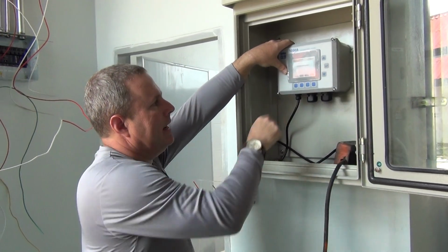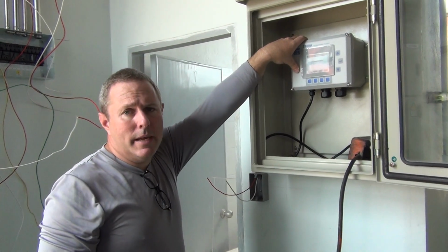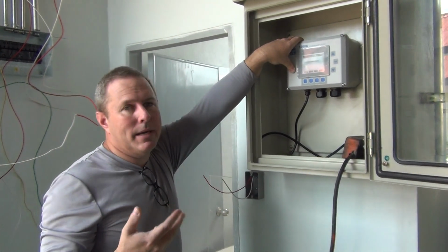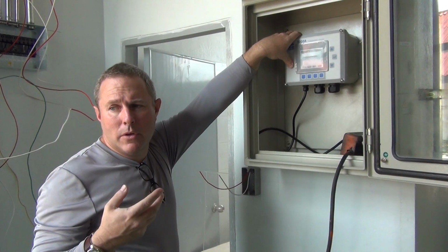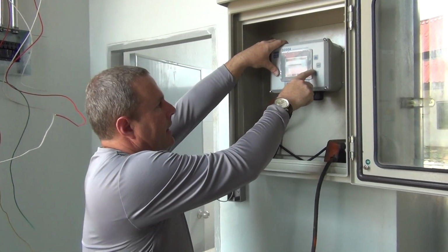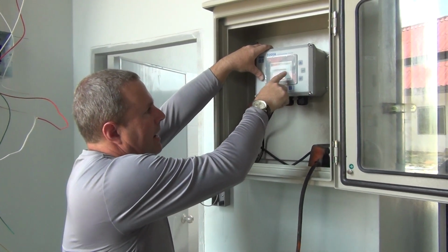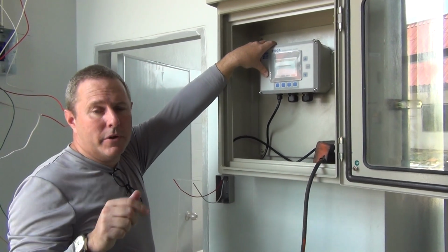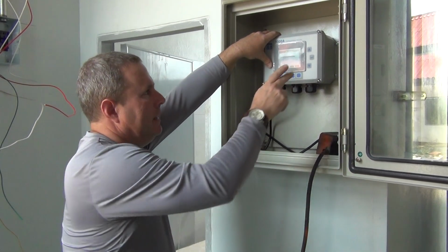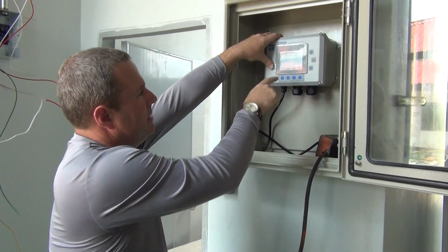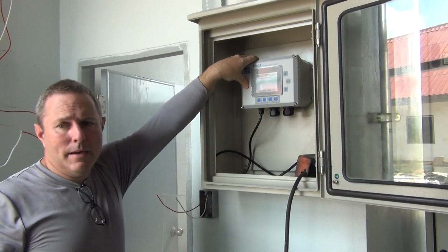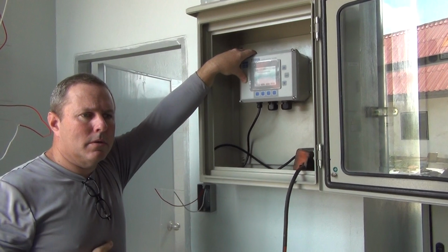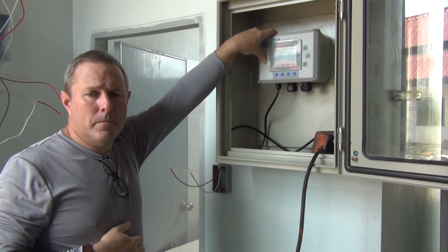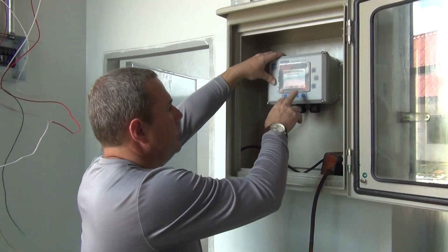Backlight timing enabled. It's an LCD screen, so we do want it backlit because without it, it's very difficult to read. So we normally leave that on, and you can control how long it stays lit after you use a keypad. I believe it's probably set for 30 seconds. It is. Is that enough time, or do you want to make it longer or shorter? I think it is okay. 30 seconds is okay. Is okay? Then we will go back.